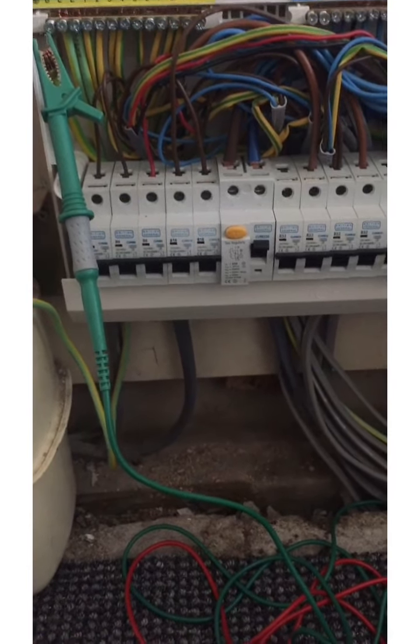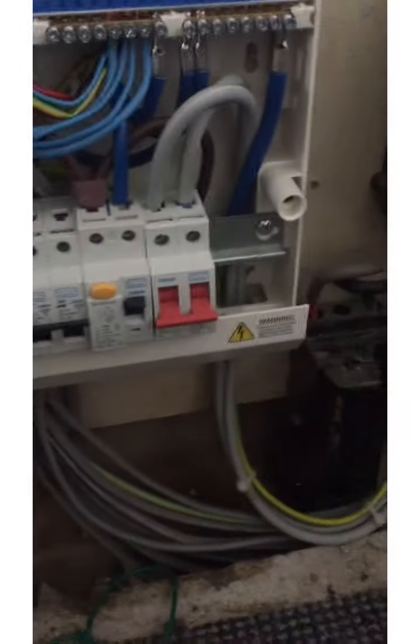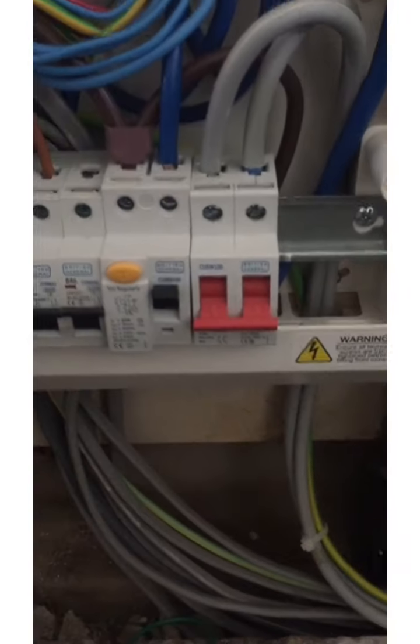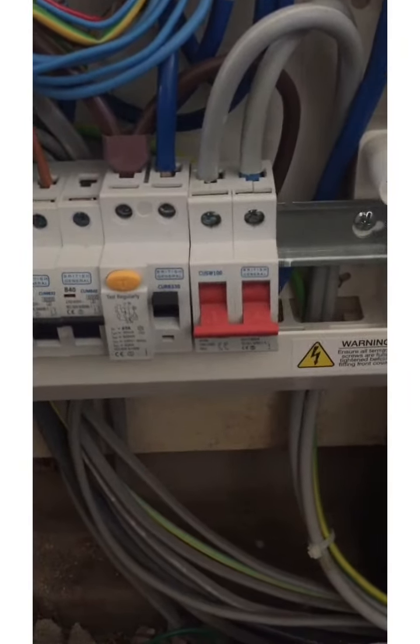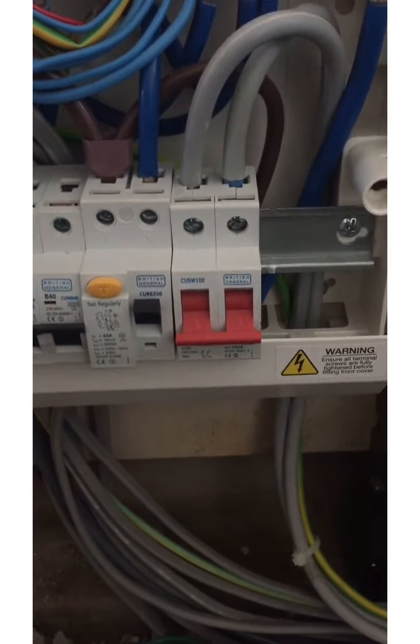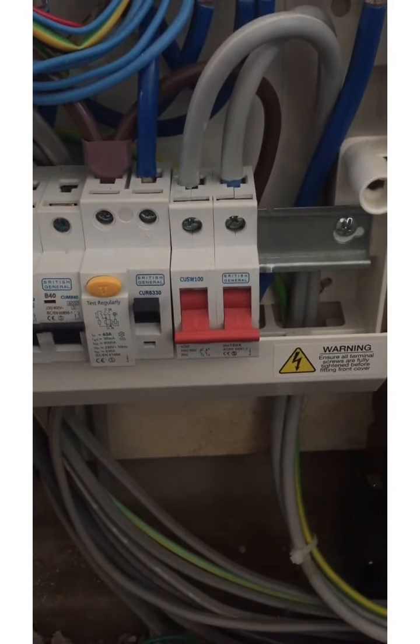Also in the guidance, another thing to realise is that we can do this test as an alternative to an earth electrode test. That's in the regs and all the guidance as well. If you think about the setup, the installation is isolated from the supply. Now, do I need to lock that off? Well, before we bowl in and do this, there's a whole load of things to think about, isn't it?